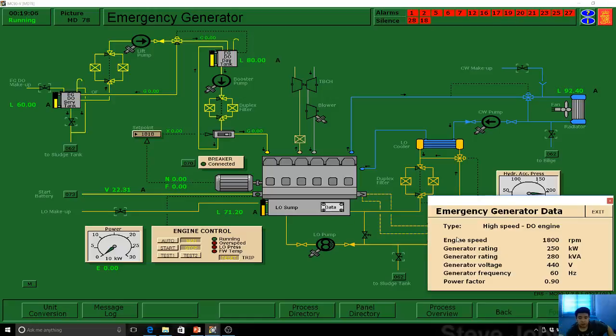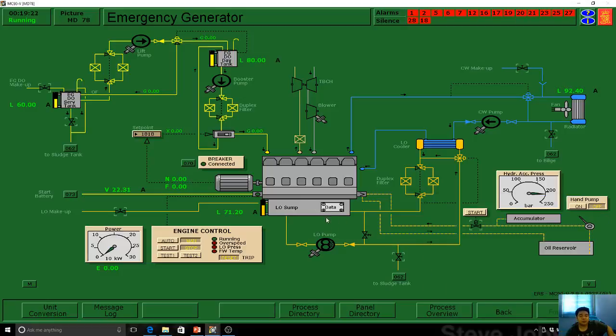The data of the emergency generator shows: speed is 1800 RPM, 250 kilowatts, 280 kilovolt-ampere, 440 volts, 60 hertz, and a power factor of 0.9. We can discuss the power factor and KVA later, but first let's start running the emergency generator.